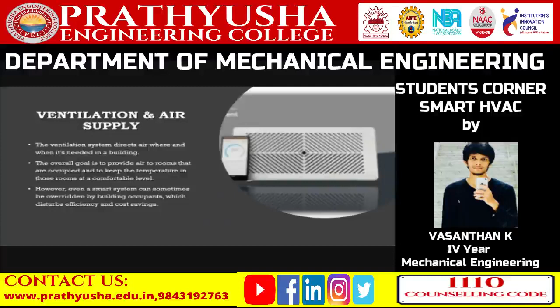Even a smart system can sometimes be overridden by building occupants, which disrupts efficiency and cost savings. Imagine a janitor, for example, who cleans a building at night. If the building has been programmed to go from 76 degrees Fahrenheit to 85 degrees Fahrenheit at 6 p.m., and the janitor overrides this functionality by turning the thermostat to 70 degrees Fahrenheit each evening as he works, that's a clear and definite misuse of the system.